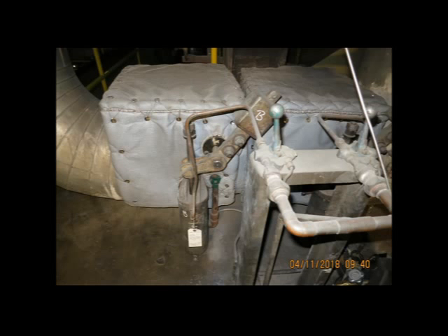And so we came on site with a helium leak detector, sprayed around, and we found that they had recently done some maintenance on an abandoned drain, and there was originally a steam sealed packing gland on this valve here.